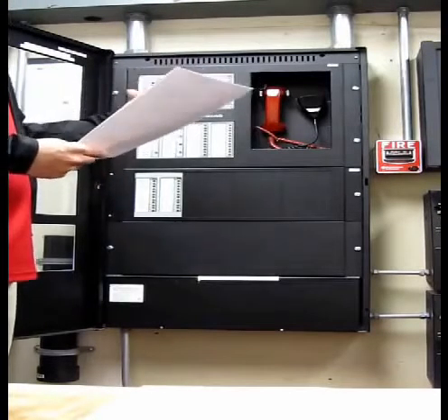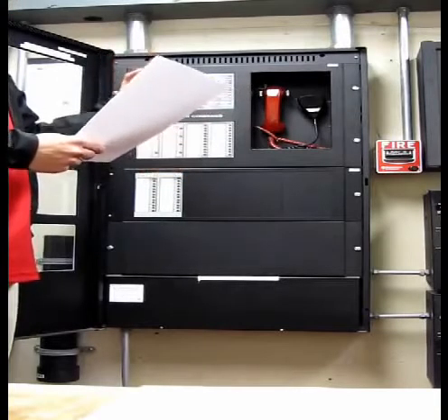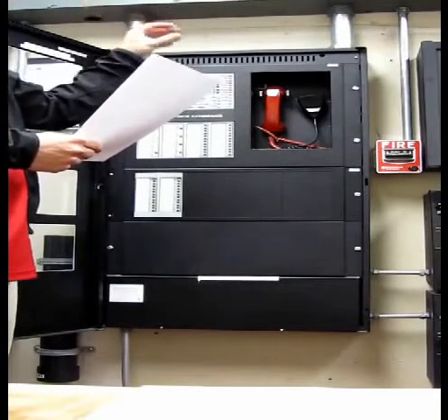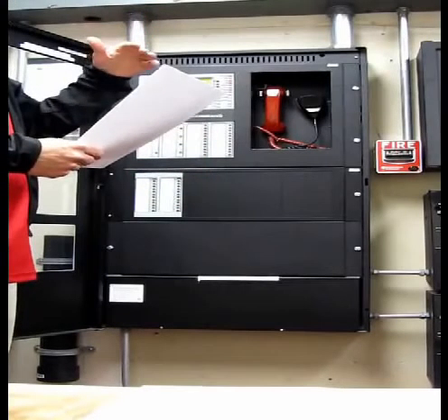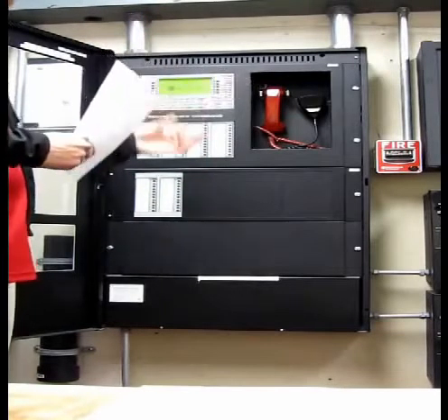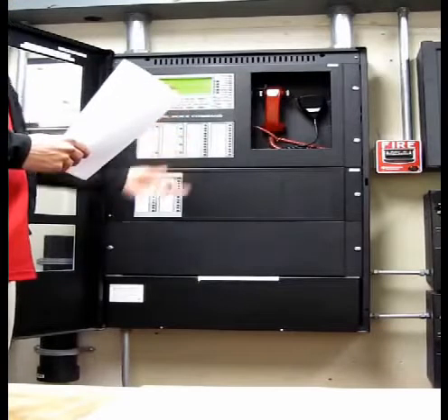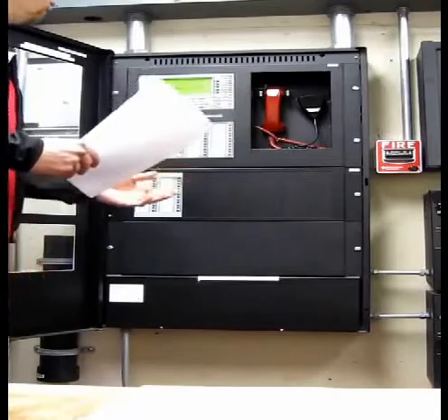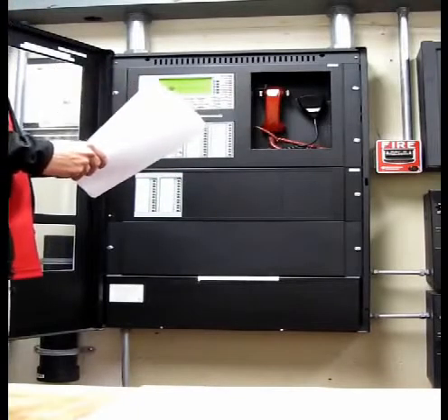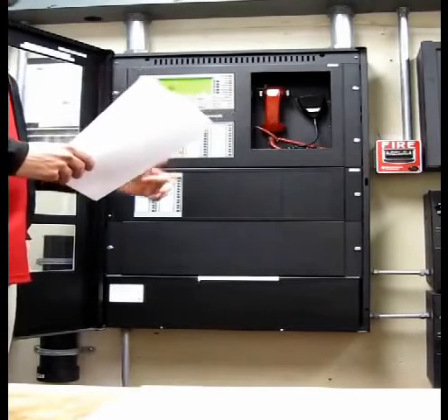A fire alarm is the opposite, it's latching. Once you pull a pull station or smoke goes into a common area smoke detector or heat, they lock into alarm. The only way to get it to clear is to remove the source in the field, and then reset the panel. So far you guys understand the difference between supervisory and trouble? Yeah. Okay, so we'll move on to alarm. If you guys have any questions, jump in at any time.